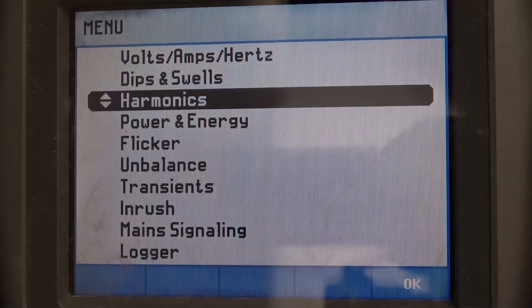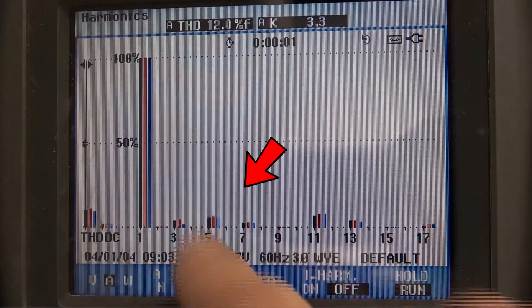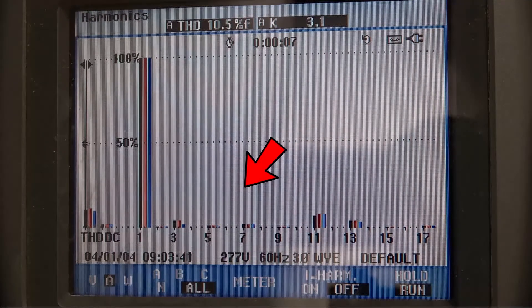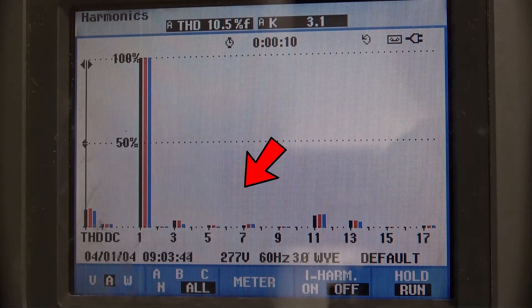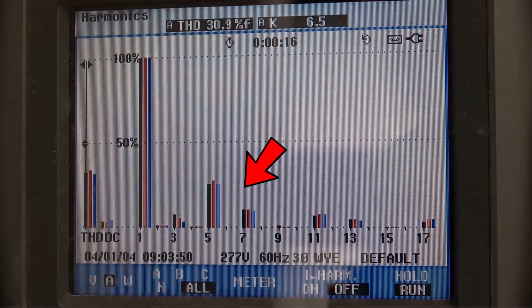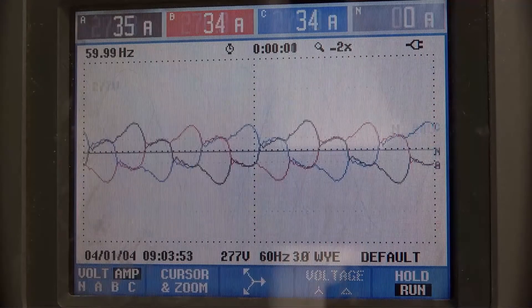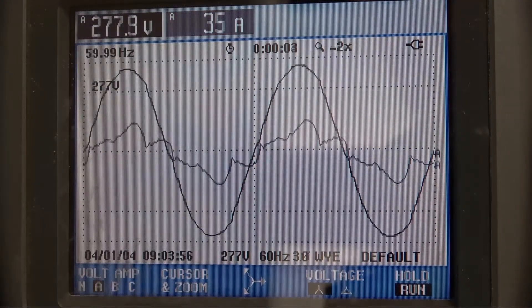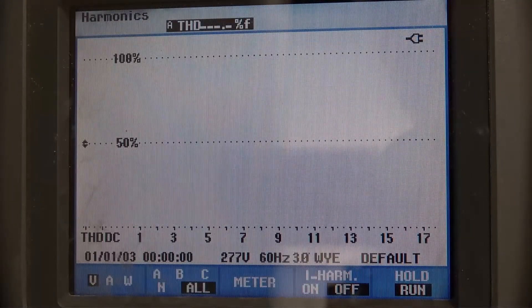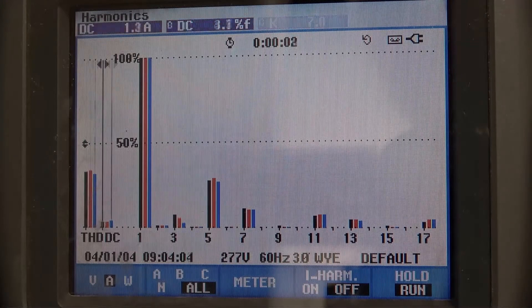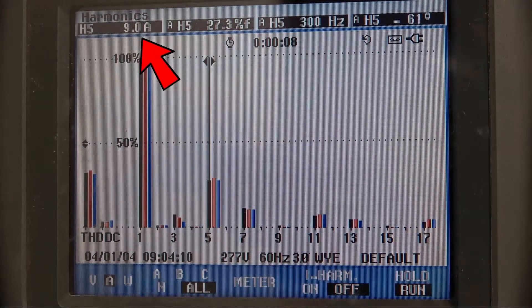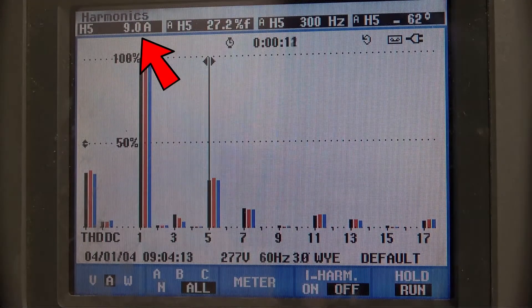Looking at the harmonic spectrum, the fifth and seventh harmonics actually go away. If we turn drive number one off, the harmonic currents come back from the drive that went through the delta-Y transformer, and we can see the wave shape is a little bit different. Looking at just the fifth harmonic on phase A, the fifth harmonic is 9 amps at minus 62 degrees.